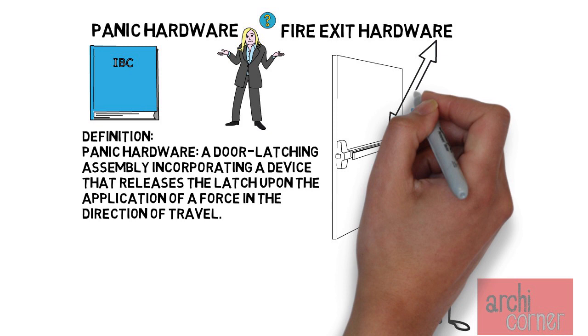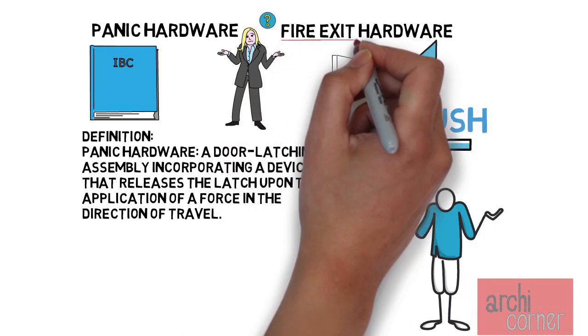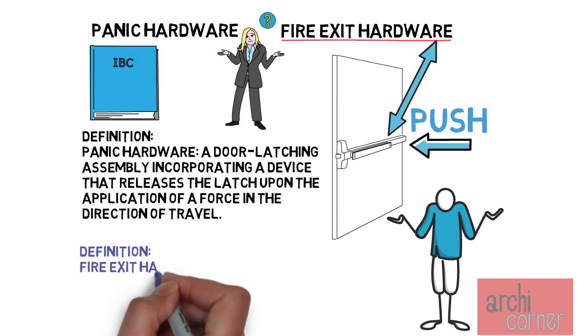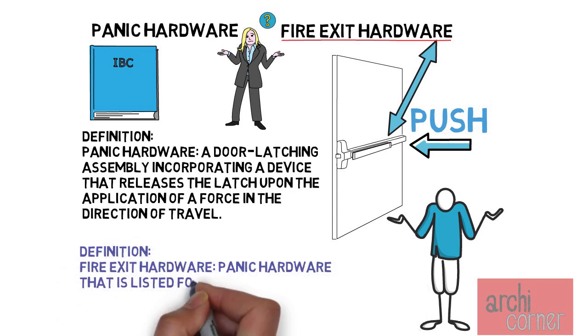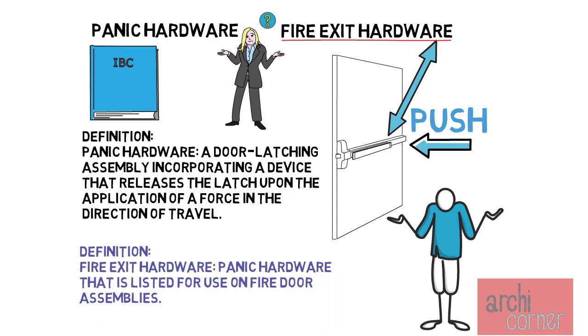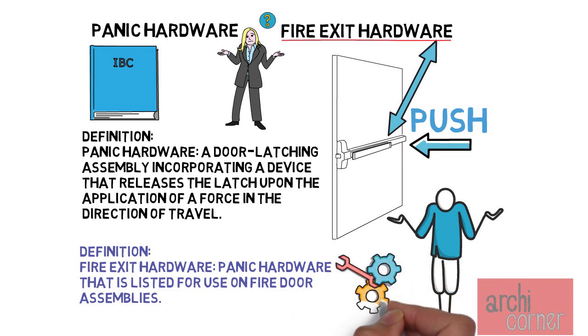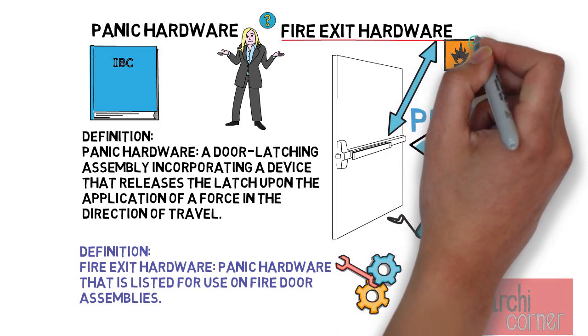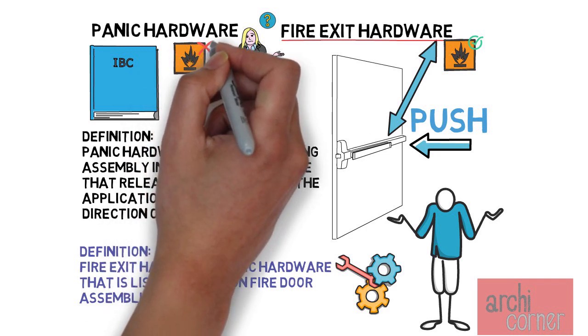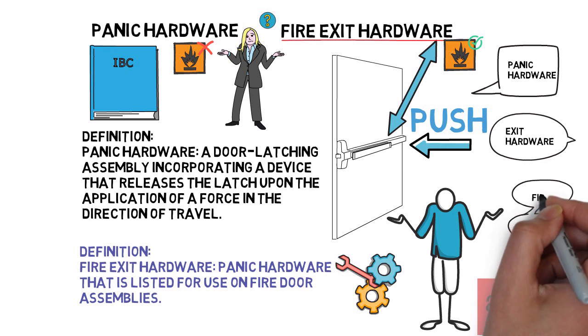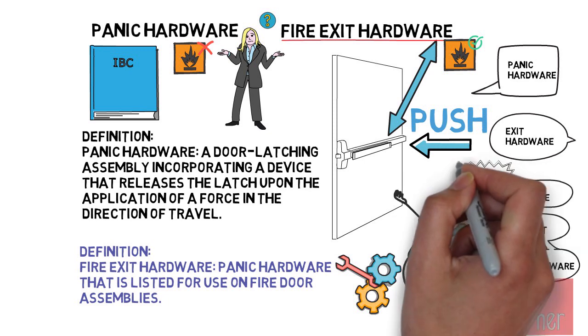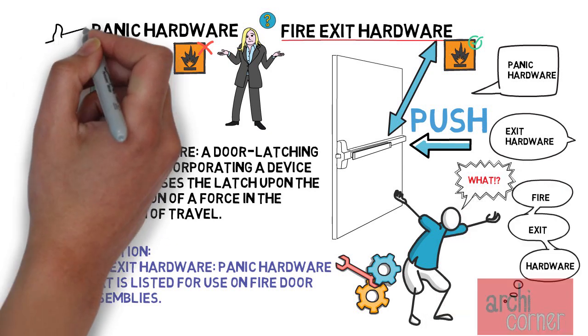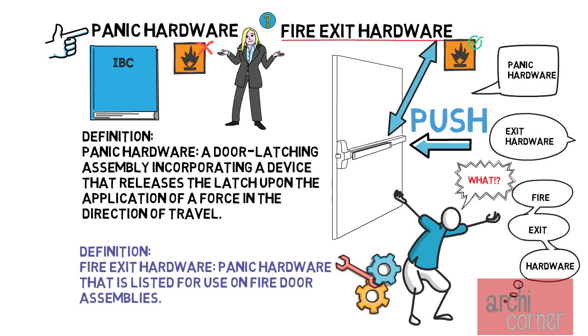So what is the difference between panic hardware and fire exit hardware? The code definition for fire exit hardware is panic hardware that is listed for use on fire door assemblies. From a mechanical aspect they both provide similar operation to open the door, but from a fire rating standpoint one can be used on a fire rated door assembly and the other cannot. For the purposes of this video we will use the term panic hardware, but keep in mind that fire exit hardware is allowed in fire rated conditions while panic hardware is not.